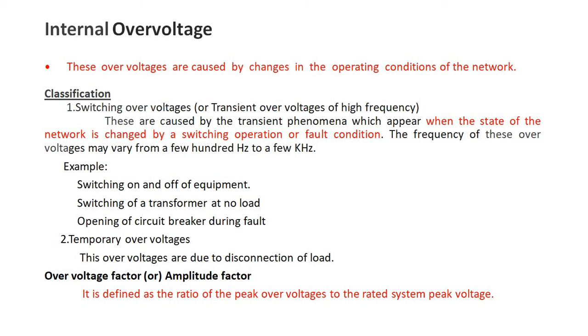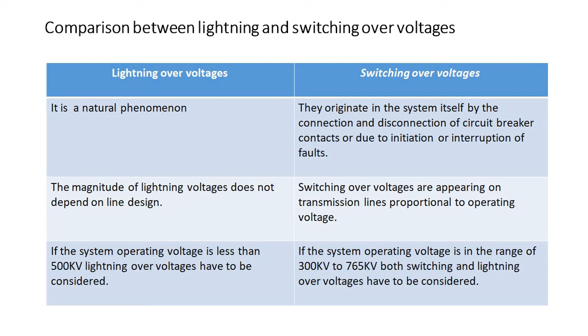Comparison between lightning and switching overvoltages. Lightning overvoltages are a natural phenomenon. Switching overvoltages originate in the system itself by the connection and disconnection of circuit breaker contacts or due to the initiation or interruption of faults. The magnitude of lightning voltages does not depend on line design. Switching overvoltages appearing on a transmission line are proportional to the operating voltage. If the system operating voltage is less than 300 kV, lightning overvoltages have to be considered. If the system operating voltage is in the range of 300 kV to 735 kV, both switching and lightning overvoltages have to be considered.